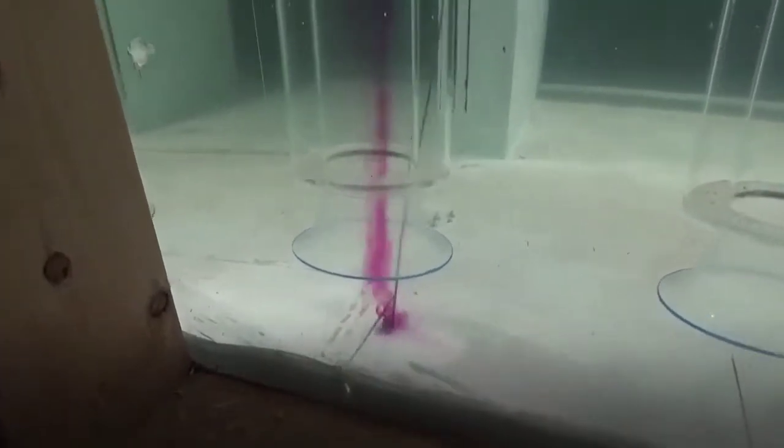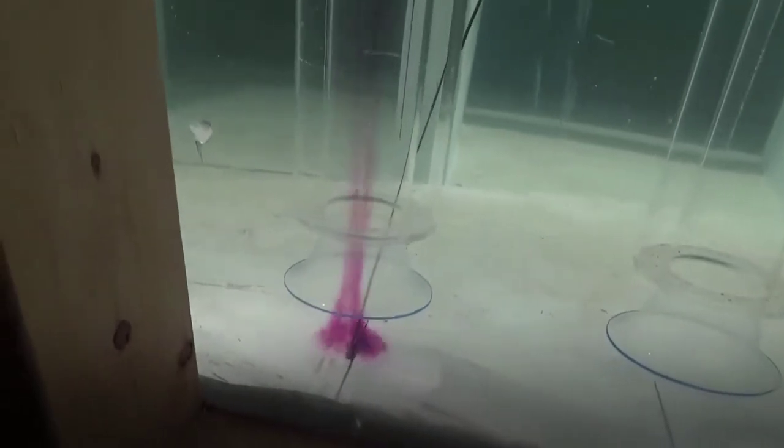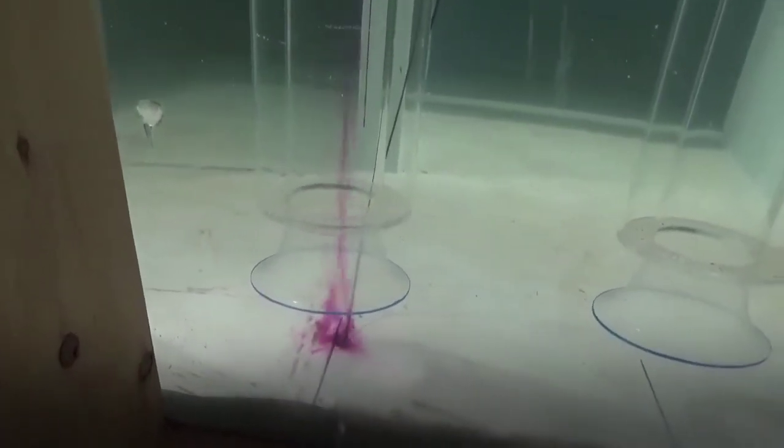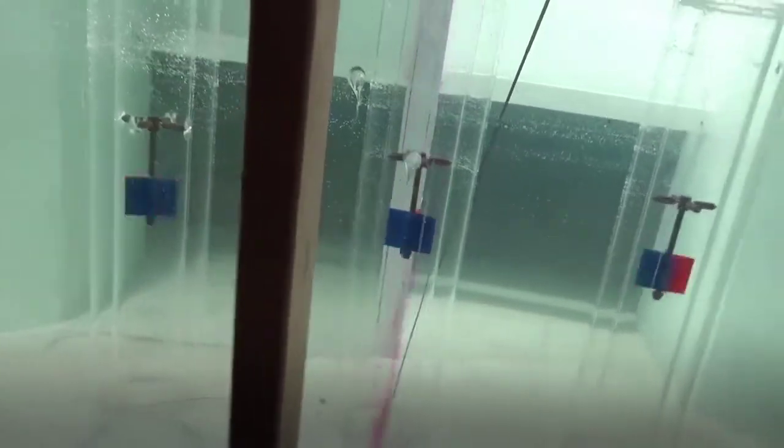You see the same thing. So we don't know how much of this is due to the vortex activity or how much of it's due to the circulation. But this one's got strong vortex activity, but very little pre-swirl in that pump right now. So it's probably a combination of the two.